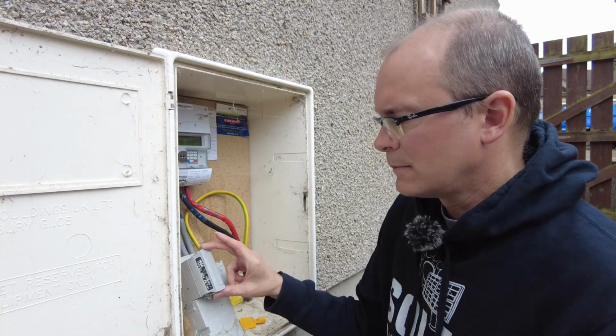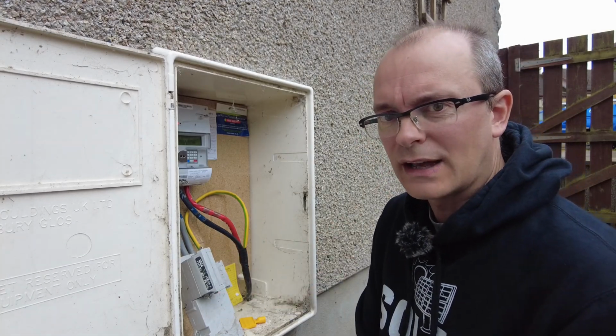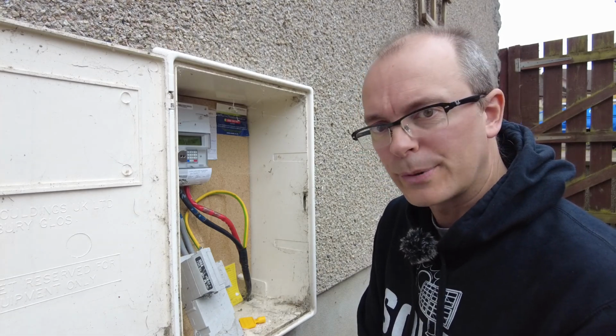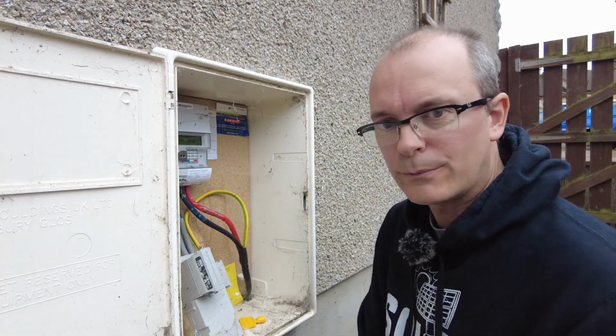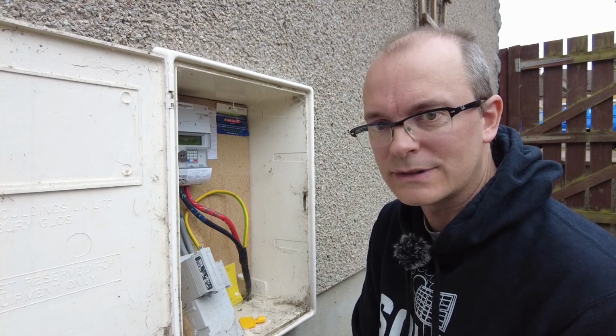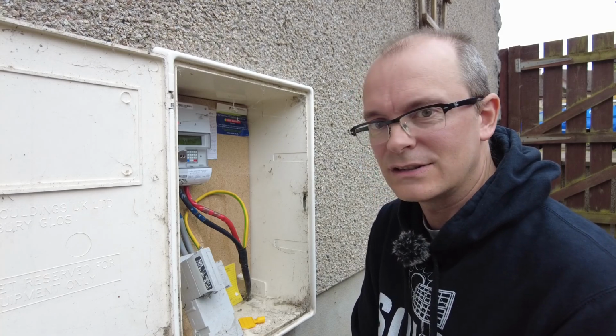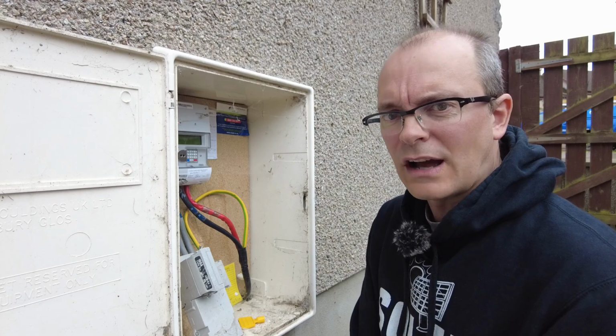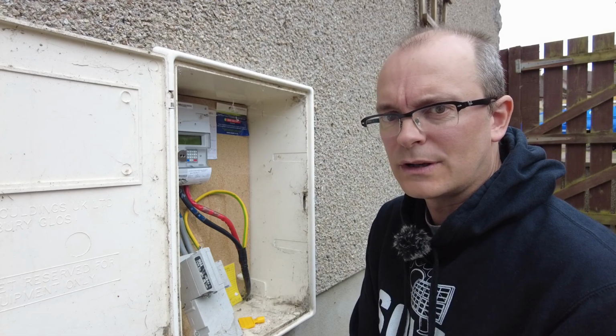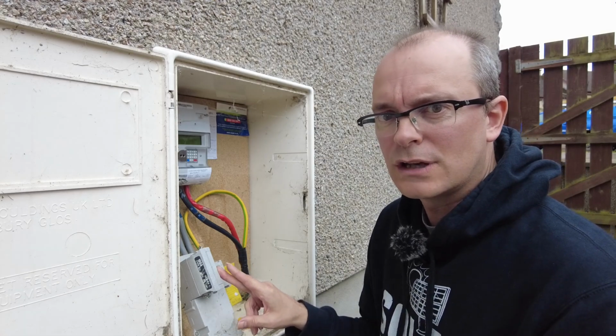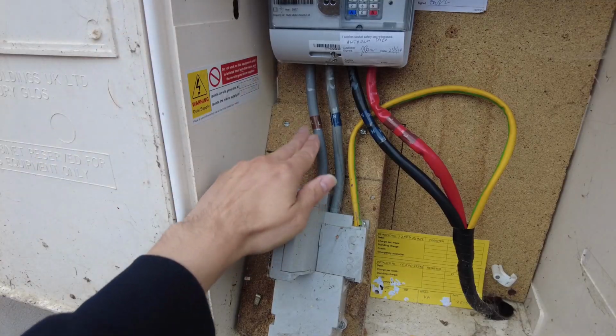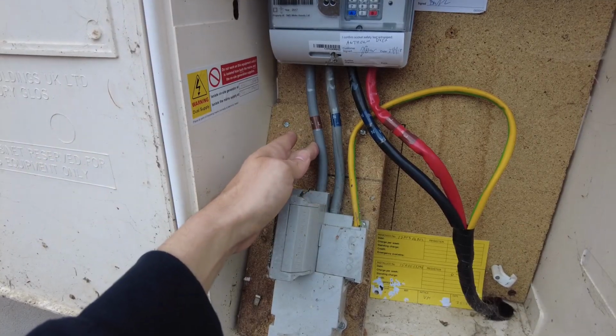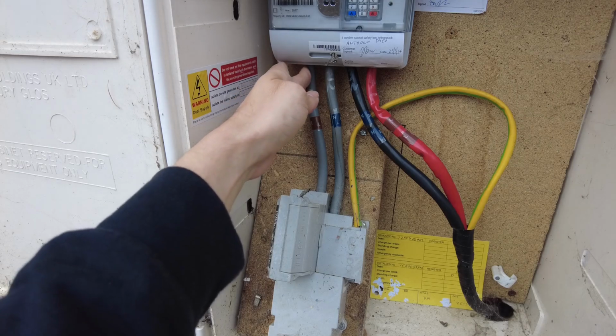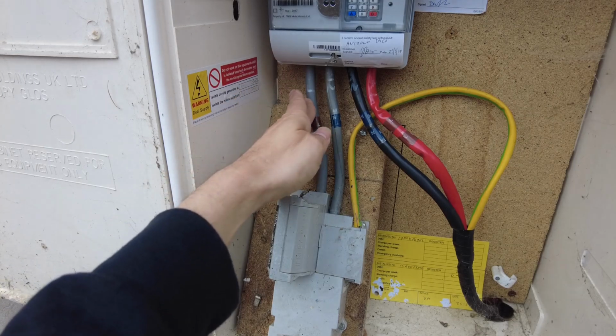Now, I can't pull this open and have a look at the rating of the fuse. It's not my property. There is a seal here. If you break the seal, you're committing criminal damage. That will certainly be the attitude of the DNO. But there are other clues in here that we can use to determine what the rating of this fuse could and likely is. So the cable going from the fuse cutout to the meter is 25 square millimeters.